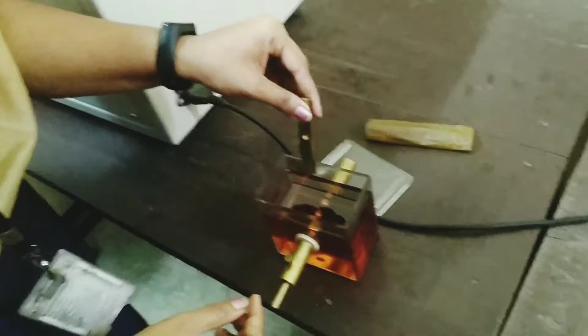You can see I can insert this rod like this, and tighten these electrodes so that it gets fixed. So the thickness or width here is 2.5 mm, which means the distance between the two electrodes within this transformer oil is 2.5 mm.